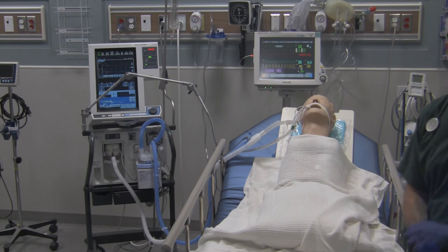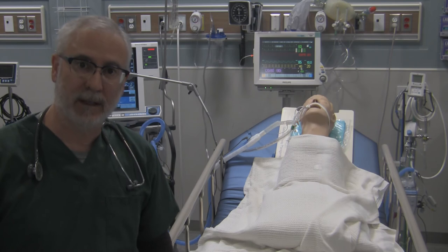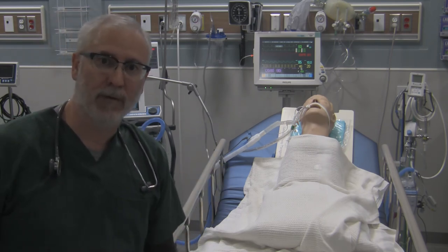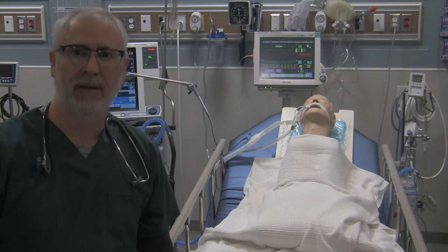The alarm you hear now is from another patient's ventilator. With closed suction systems, always make sure that after you're done suctioning your patient, you return the suction catheter to its proper position. That way, volume delivery won't be affected in pressure ventilation, nor will high pressure alarms trigger if you're volume ventilating. This has been George with hopefully a handy ventilation tip for you. Have a great day.